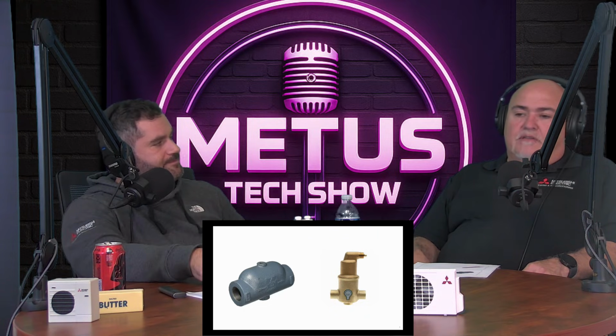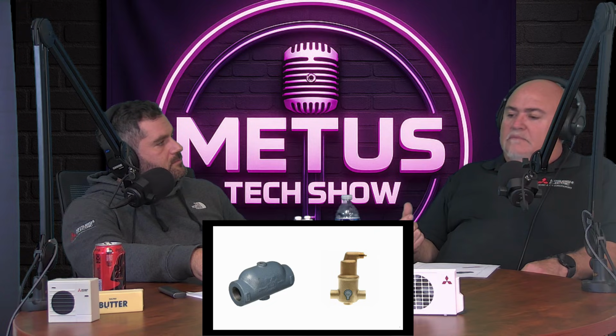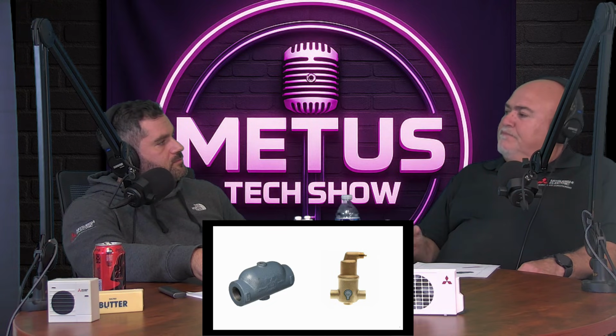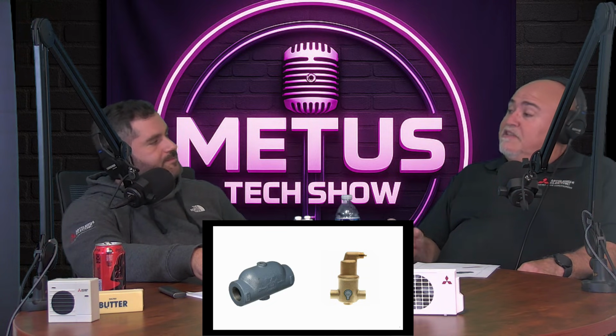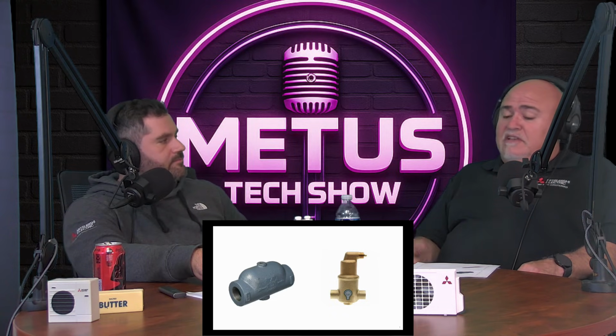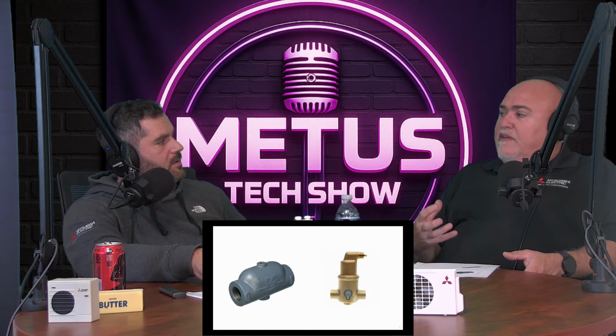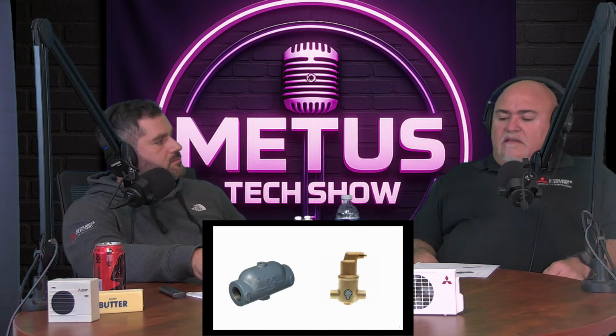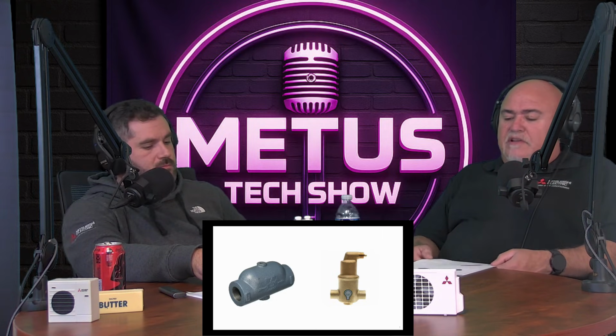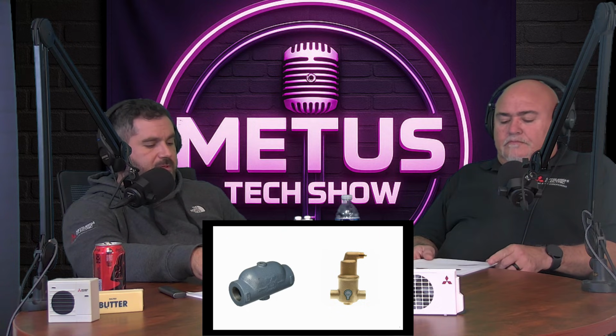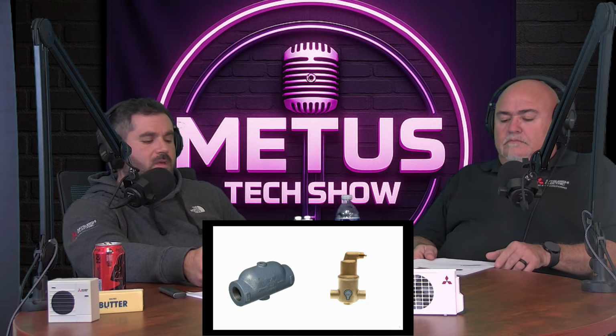Much more efficient than a small automatic air vent that would go on a T or something, and a lot of air would bypass and not be able to be released, where this grabs all of that air, or most of it, and vents it right out. So really efficient air vent. Yep. Yeah, they're definitely something you need to have on a hydronic system.